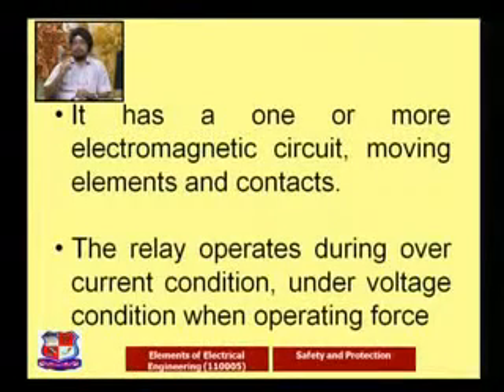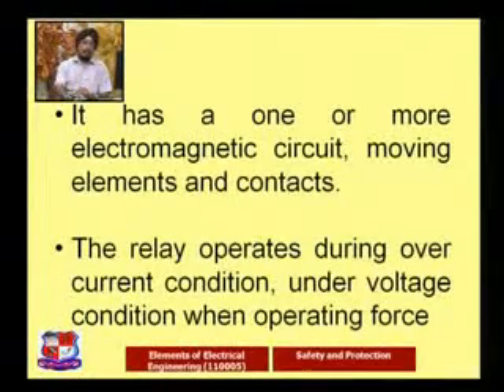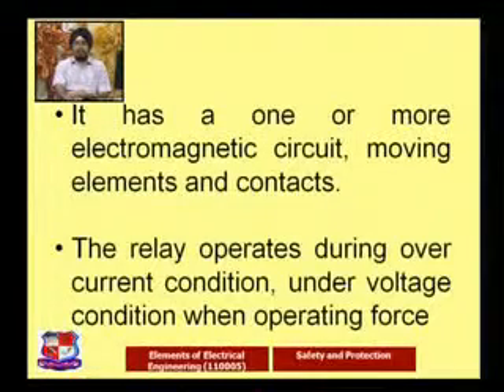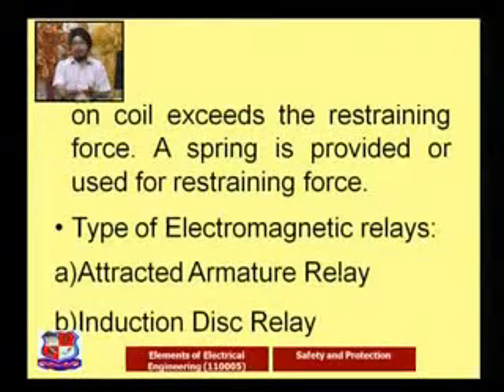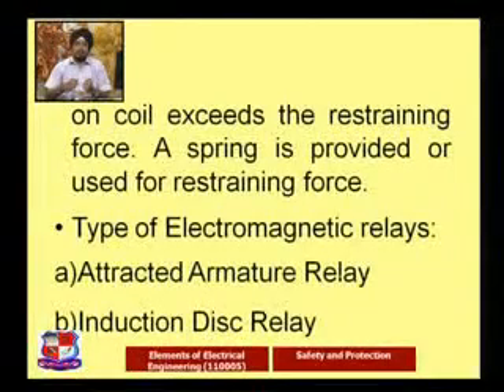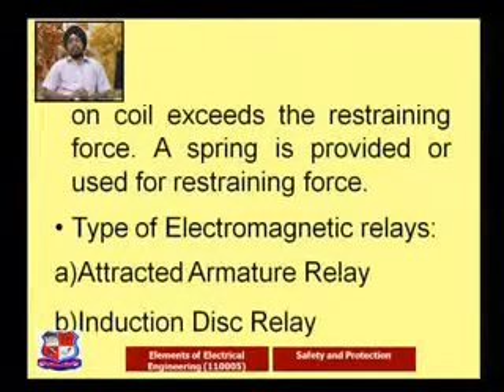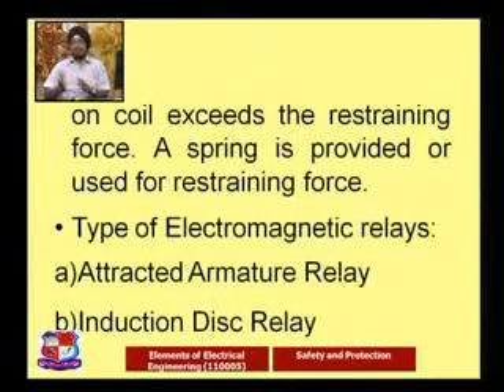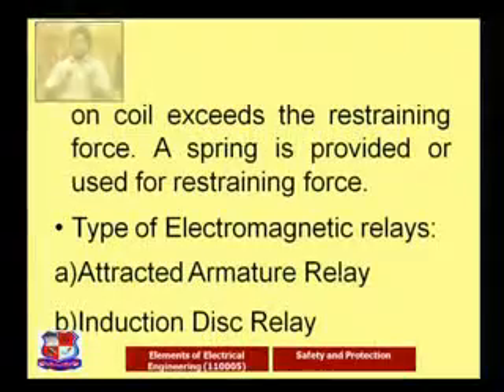Those contacts are going to touch, or come into contact with the tripping circuit, where the tripping is going to be done. The relay operates during an overcurrent condition or undervoltage condition, when the operating force on the coil exceeds the restraining force. Now two types of force are there, the operating one and the restraining one. The restraining one stops operation in the normal condition, but when it exceeds some limit, the operating force becomes much higher than the restraining one, and our contacts are going to close.